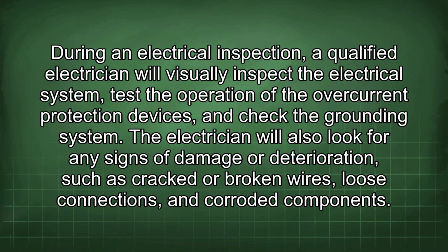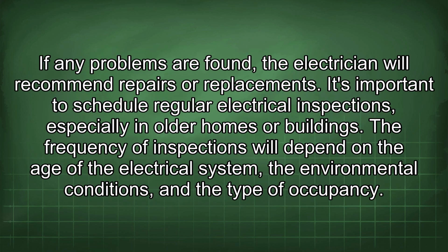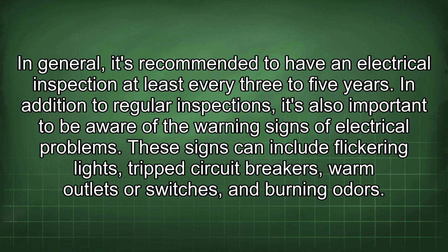During an electrical inspection, a qualified electrician will visually inspect the electrical system, test the operation of the overcurrent protection devices, and check the grounding system. The electrician will also look for any signs of damage or deterioration, such as cracked or broken wires, loose connections, and corroded components. If any problems are found, the electrician will recommend repairs or replacements. It's important to schedule regular electrical inspections, especially in older homes or buildings. The frequency of inspections will depend on the age of the electrical system, the environmental conditions, and the type of occupancy. In general, it's recommended to have an electrical inspection at least every 3 to 5 years.